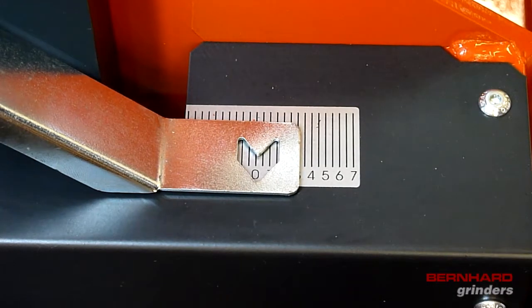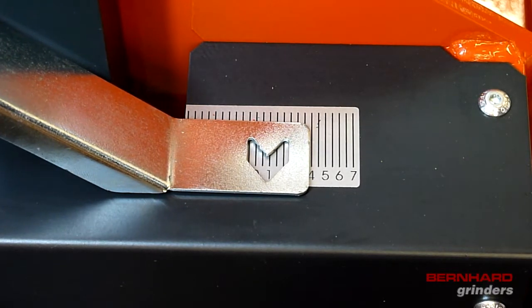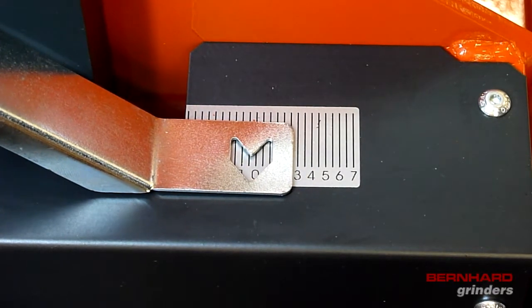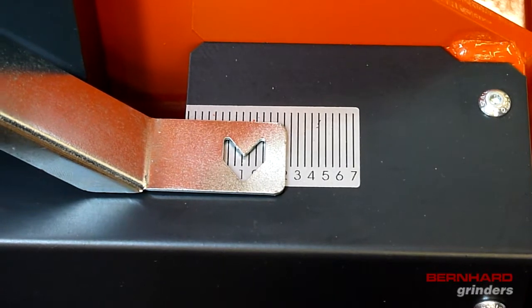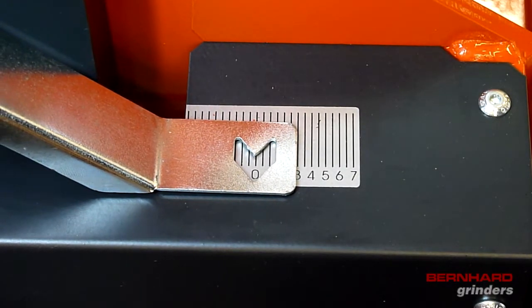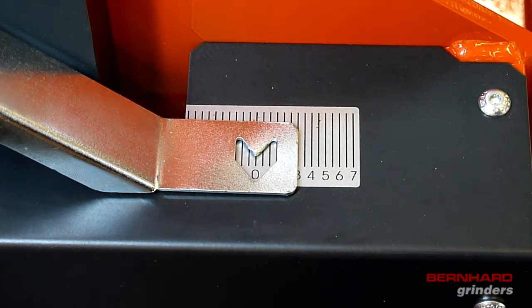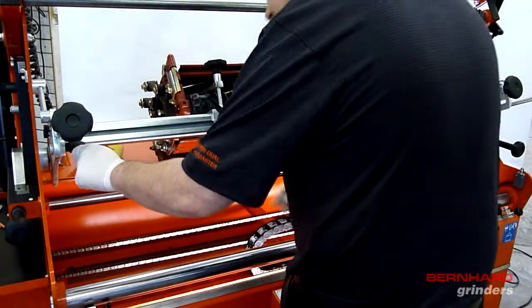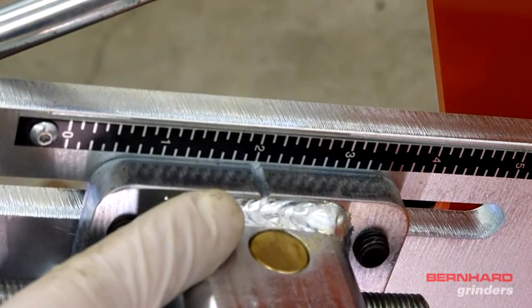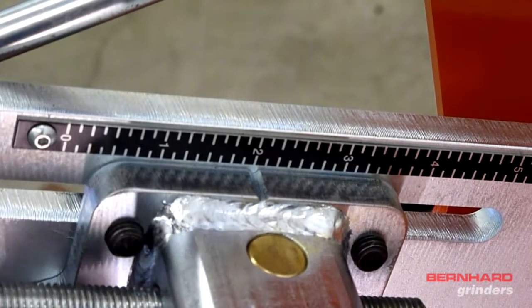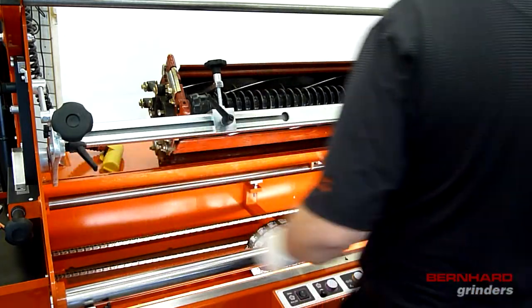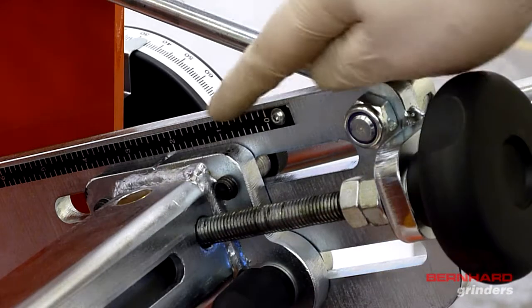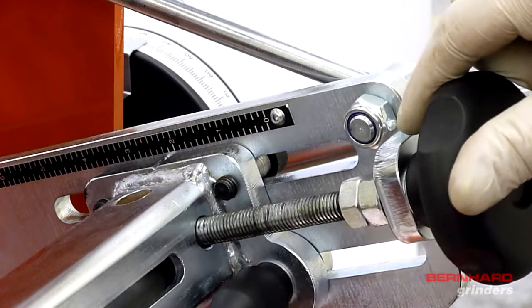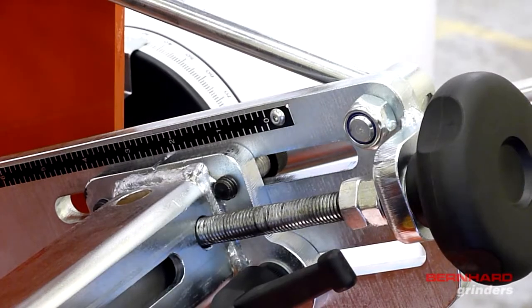Before making any adjustments, ensure that the mounting bar is squared and parallel. Make sure the fine adjusters on each end are set to 0 and that each side of the mounting bar is even. Here we can see the mounting bar being set to 2 on both sides. When the locations are even, lock off the mounting bar by tightening the clamp levers.